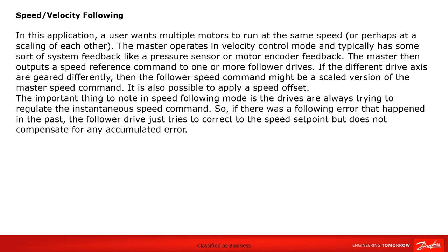Speed velocity following. In this application, a user wants multiple motors to run at the same speed, or perhaps a scaling of each other. Here the master operates in velocity control mode, and it typically has some sort of system feedback. It could be a pressure sensor, or here we can use a motor encoder feedback. The master then outputs a speed reference command to one or more of the follower drives. If the different drive axes are geared differently, then the follower speed command might be a scaled version of the master speed command. And it's also possible to apply a speed offset.